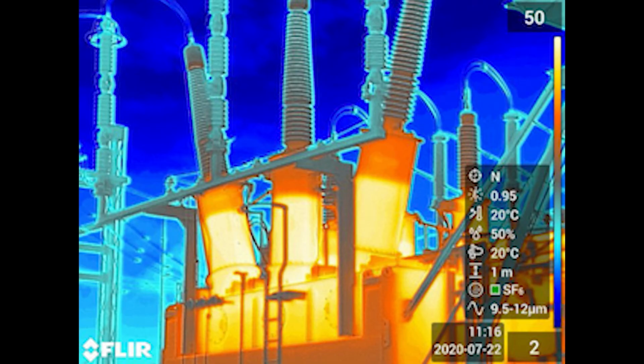This is the exact shot with the GF77 in IR mode. We are looking for hotspots and heat inside the transformer. After looking at this image in the FLIR thermography software, we determined that Phase 1 was running at 48.1 degrees Celsius, Phase 2 at 48.8 degrees Celsius, and Phase 3 at 48 degrees Celsius. Although it appears hot, the transformer is operating within normal parameters. Since there is no temperature differential between the phases, there's no cause for alarm.